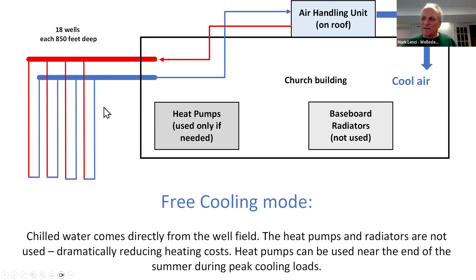So our most economical mode of operating this is the cooling mode. Believe it or not, air conditioning is almost free—not meaning free in the technical 'free cooling' sense only, but also economically almost free. The heat pumps can kick in if, by the end of summer, we've heated up the ground out here and the water has heated up. We've yet to see that happen.